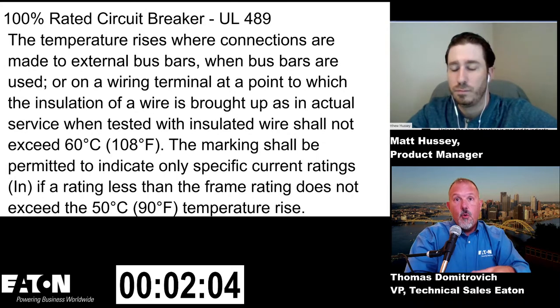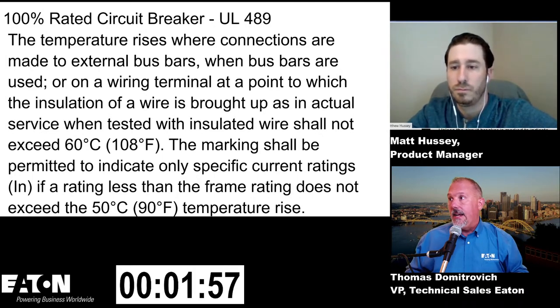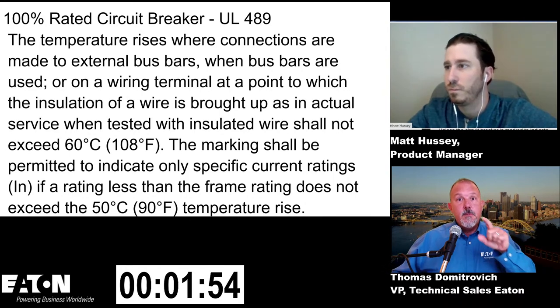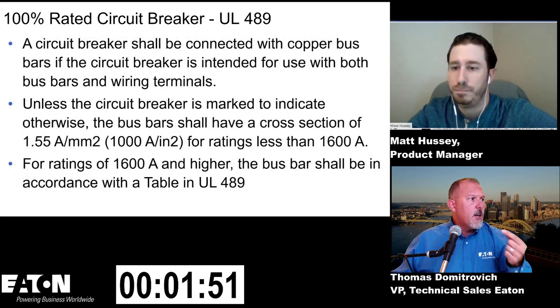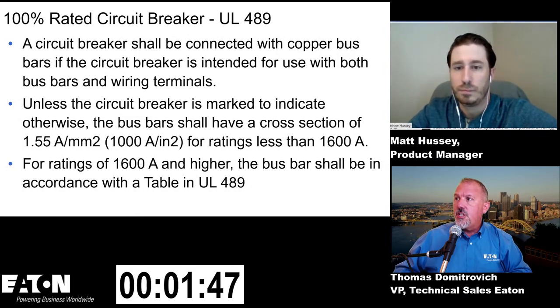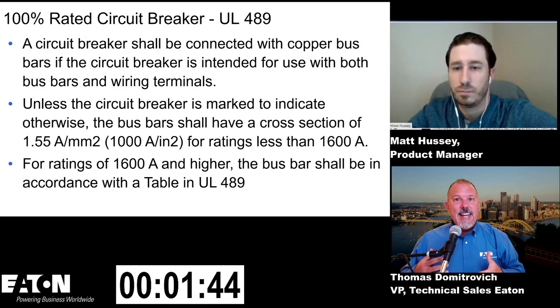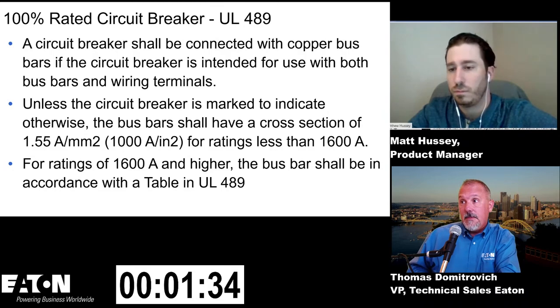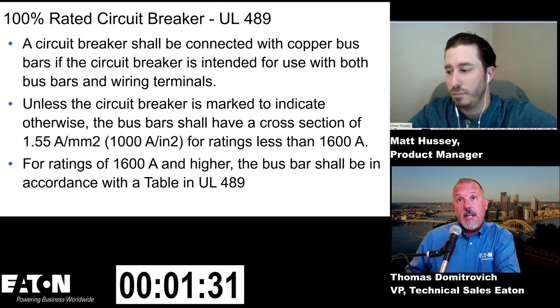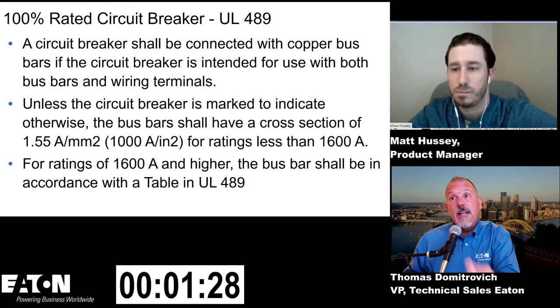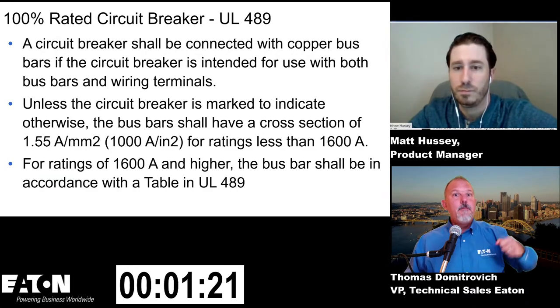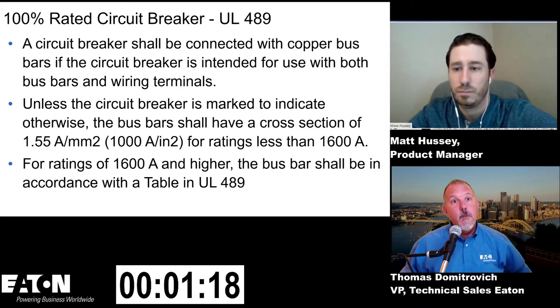That assembly with the breaker needs to be labeled, but also the equipment that it's in, because if I look at UL489, it talks about the size of the enclosure, right? It also talks about how a circuit breaker shall be connected with copper bus bars. So I can't have an assembly like a panel board that has an aluminum bus. If it's going to be 100% rated, it's definitely going to be a copper bus. And in some cases, I might have a panel board that has a specific density of copper as a bus, because I've got to pull out the heat that I'm not getting from the conductors on the load terminals of the breaker.